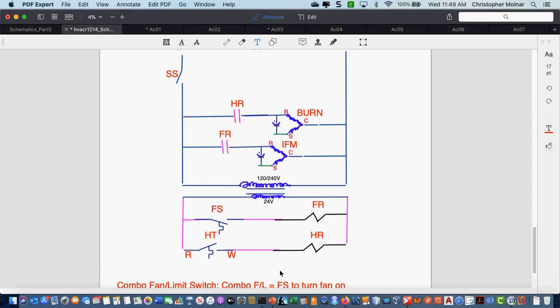Right. So anytime I place a limit switch, I could put it here. A lot of times you see a limit switch on the line voltage side, or I could put it on the low voltage side, which is getting more and more frequent. So I could put a limit switch between line and HR, or I could put a limit switch after W going to HR. Personally, I like putting limit switches up on the HR side.